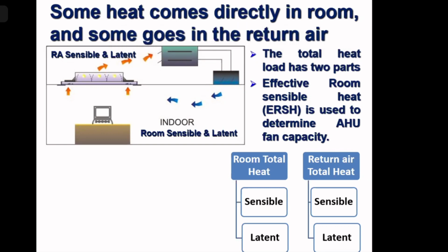And the heat which is going to the return air part has nothing to do with how much cold air we supply in the room. But that air also has to be cooled. That heat also has to be cooled by the cooling coil. So the cooling coil has to be sized for the room total heat, that is sensible and latent, because for sensible heat we have to recool the return air, which is picking up heat from the room. So room sensible heat finally has to be cooled in the cooling coil. So that will form one part of the cooling requirement of the cooling coil. Then the latent heat from the room, by way of moisture, goes to the cooling coil, and it also has to be condensed out by the cooling coil.